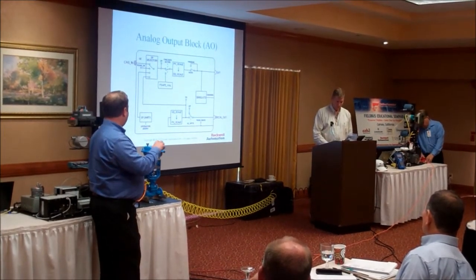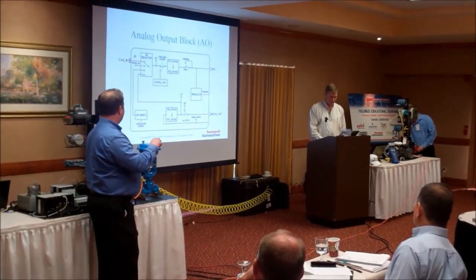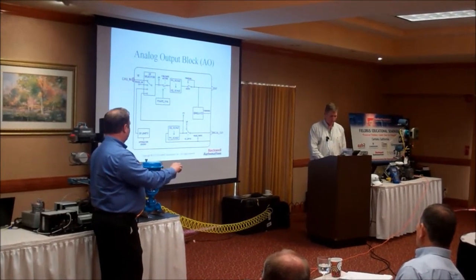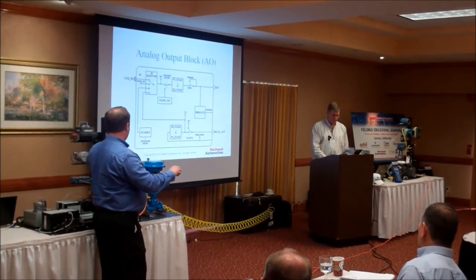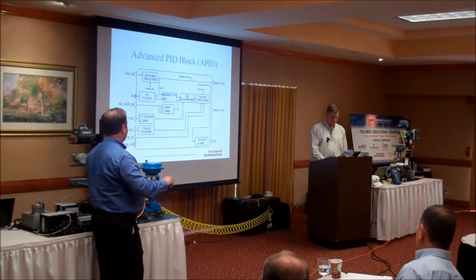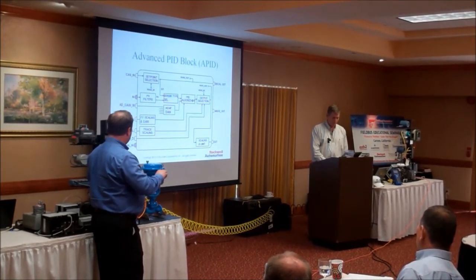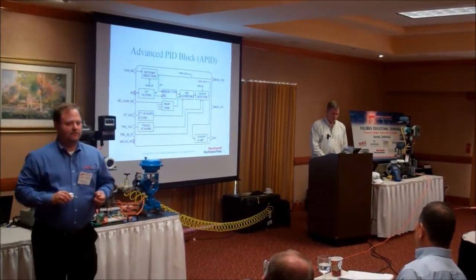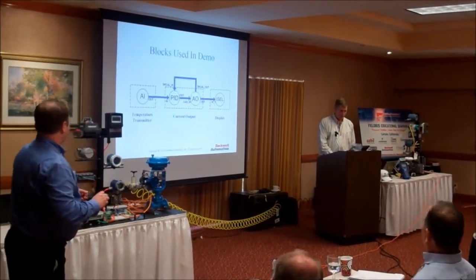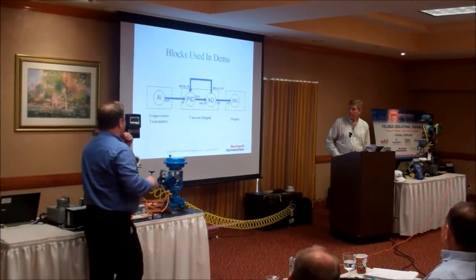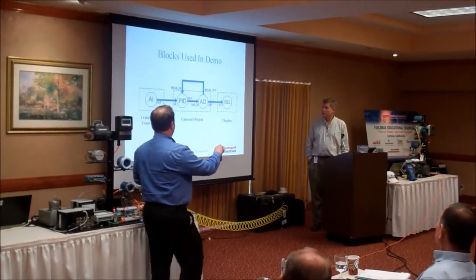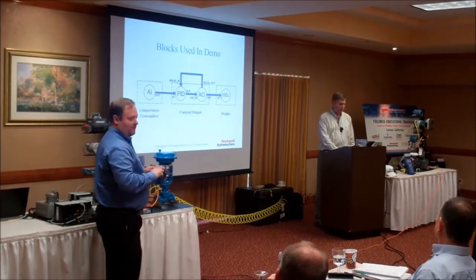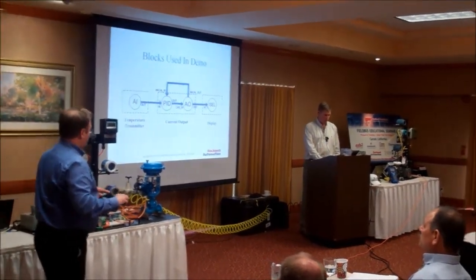Additionally, we have an analog output, which will be taking the signal from the PID and going out to the display. And additionally, the back-calculation output will go back to the back-calculation input on this PID right here. Does that make sense? So it's going to look like this — the temperature transmitter, the current output, and the display. This is all the function block layers in the devices.